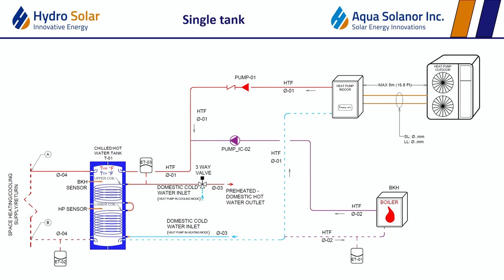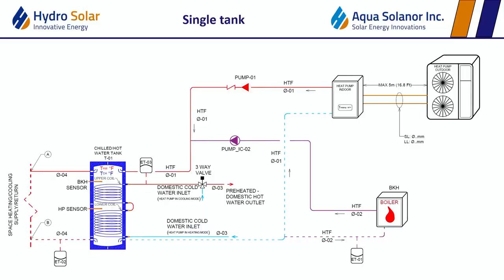You call it a conventional system, but I don't typically think of exterior systems as air to water, so this is a bit unique in the marketplace. In a way, if you replaced the water component with an air handler, it would still be on the conventional side. The difference is that on the buffer tank we have heat exchangers. If you took a conventional air-to-air source system, you could place another coil inside and preheat the incoming air into your furnace. So if your room is at 60 Fahrenheit, you can preheat that air up into the 70s, and then your furnace only has to kick it up from 70 to 80 to reach the temperature you need.